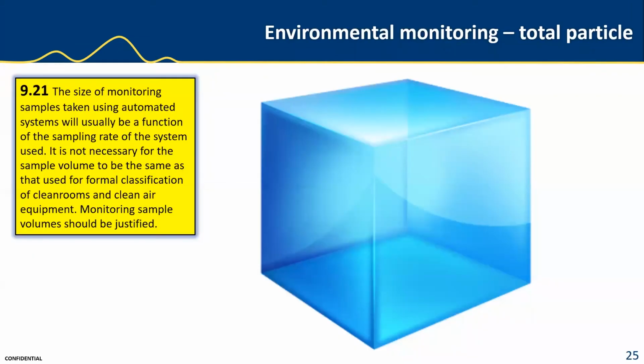If you look at section 9.21, still under total particle in the environmental monitoring stage, the size of monitoring samples taken using automated systems will usually be a function of the sampling rate of the system used. It is not necessary for the sample volume to be the same as that used for formal classification of clean rooms and clean air equipment. Monitoring sample volumes should be justified. I often see a lot of confusion regarding this one. It also adds confusion regarding setting alarms, as some people interpret the guideline incorrectly and apply sample volumes of a cubic meter into continuous monitoring systems.